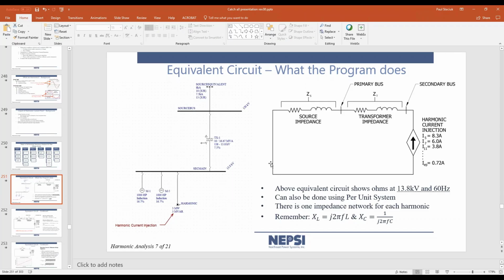What you see here on the left is a very simple system that's been modeled in EasyPower, just a source, a transformer, and then some loads. The equivalent network for this system is shown on the right. You can see there's a source impedance and a transformer impedance. And then we have our harmonic current injection to the right here. Remember, that's an ideal current source, which means that no matter what this impedance is, this current will be pushed through that impedance. Kind of like a current transformer on a network, a CT will push out secondary current no matter what its impedance is, up to a saturation point. An ideal current source will push out harmonic current to the value that's specified.